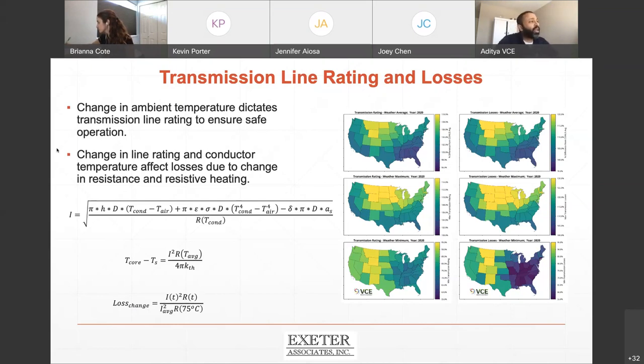The way we determine the average line ratings is we use the IEEE standard for that. Based on that, we determine the average line rating that's typically in the standards, and then figure out what additional line rating we can add. So it is not fine-tuned for PJM specifically; it is a more general methodology that we use. What PJM is doing might already have some of this included.